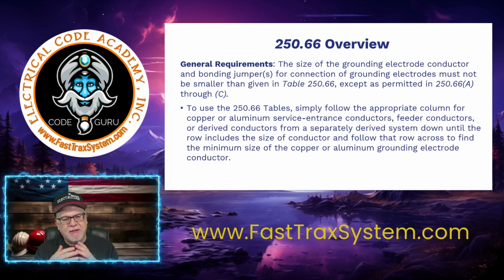Okay, for example, you might have two sets of 500 kcmil. That's a parallel set. So together that'd be 1,000. Okay, so those conductors are what we're going to help decide based on table 250.66, the size of our grounding electrode conductor, right? Now, it says, except as permitted in 250.66A through C.